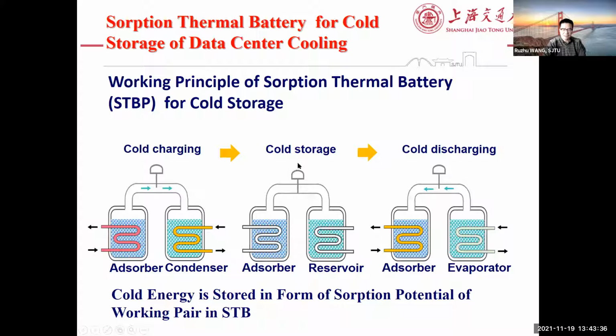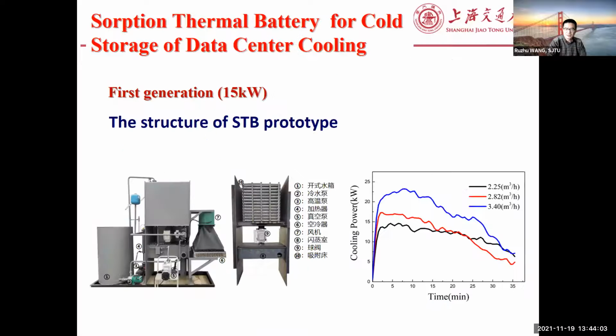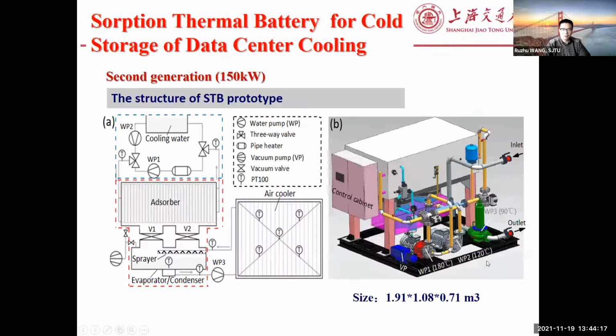And also we did some other work for data center on the so-called sorption thermal battery, and try to get 2 adsorbers when it's generated. And then separate it and then keep it. But when you need the cooling, you just open the valve and then suddenly you could output the evaporation to get the cooling. So this is a kind of adsorption cold storage. And this is at the request of Huawei, and we developed such a system. So this is the first model for about 15 kilowatt and to sustain for more than 15 minutes. So now they want us to build a 150 kilowatt. So now this is on the way of design. So it's a very compact system, but this is used certainly for a data center if electricity is shut down. Originally, they need a big backup for the electric battery.